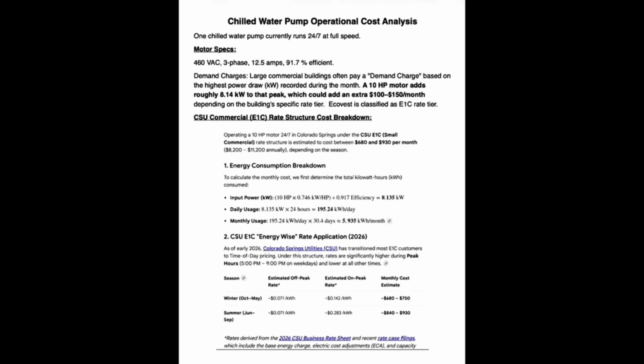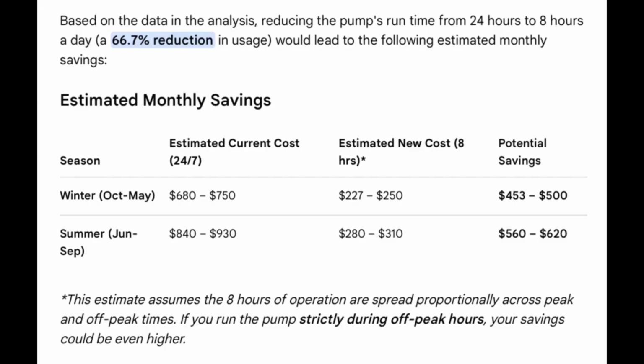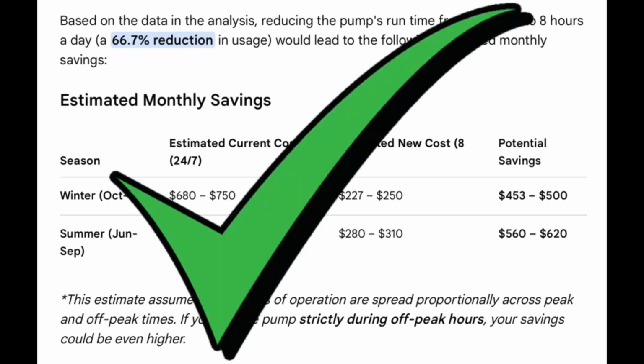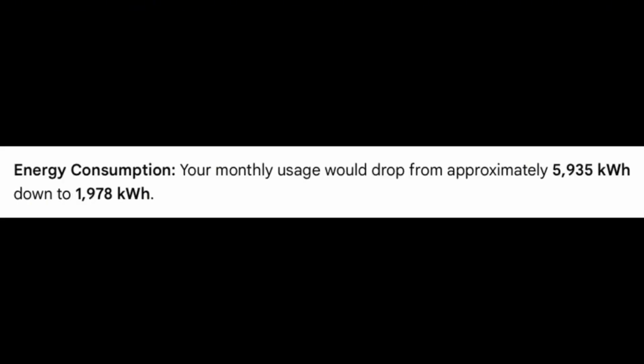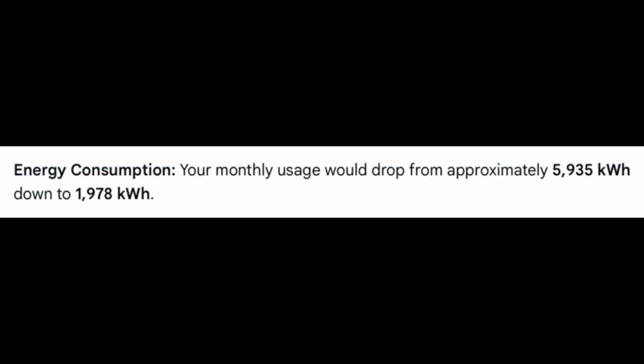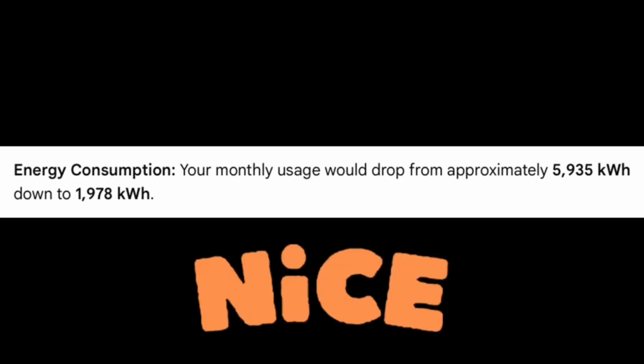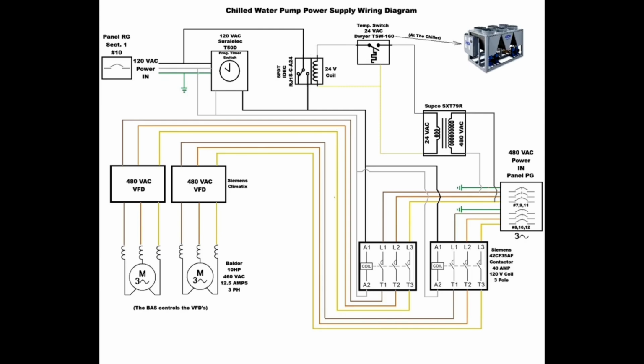And you can see the energy consumption, and of course the time of day, the time of year, the rates will fluctuate as well. So you can see by reducing the runtime to just 8 hours a day, let's say during regular business hours instead of 24/7, that's a 66% reduction, which will save us $453 to $620 a month. So that's several $1,000s a year that we're going to save by reducing that pump runtime. And that's also going to reduce the amount of wear and tear and hours on the equipment. And so our monthly energy usage or consumption would drop from 5,935 kWh down to 1,978 kWh.